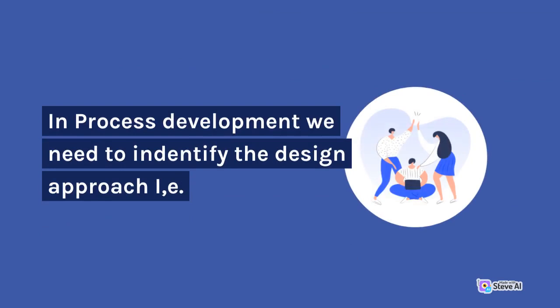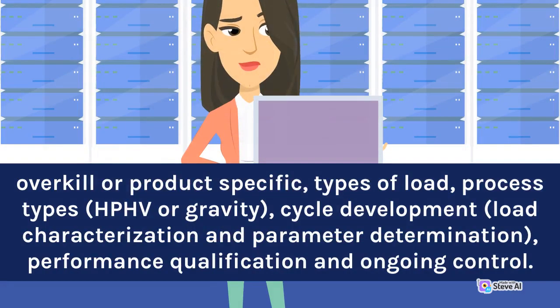Before performing validation of an autoclave, we need to first understand the process development and process qualification. In process development we need to identify the design approach, i.e. overkill or product specific, types of load, process types — HPHV or gravity — cycle development, load characterization and parameter determination, performance qualification and ongoing control.